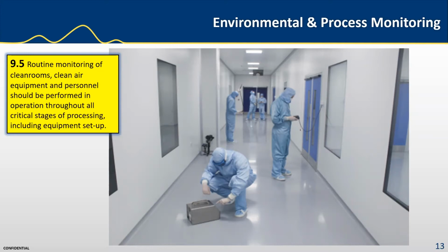The routine monitoring of clean rooms, clean air equipment, and personnel should be performed in operation throughout all critical stages of processing, including equipment setup. I recommend, if you're not doing so already, to monitor the pre and post processes, not just your process. So monitoring the pre-assembly setup should indicate that the environment meets grade A cleanliness. I would say at a minimum collect a 1 cubic meter sample volume so you can show you meet grade A cleanliness levels. The same is true for post-monitoring. When the production ends, I would gather a minimum of another cubic meter sample.